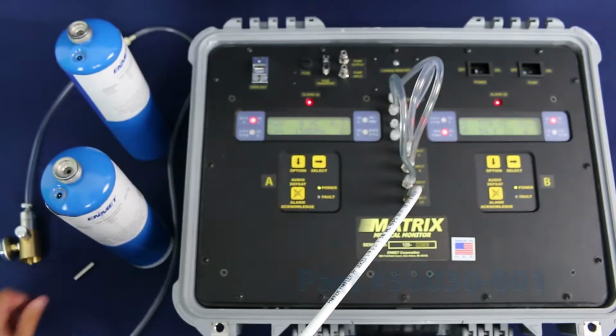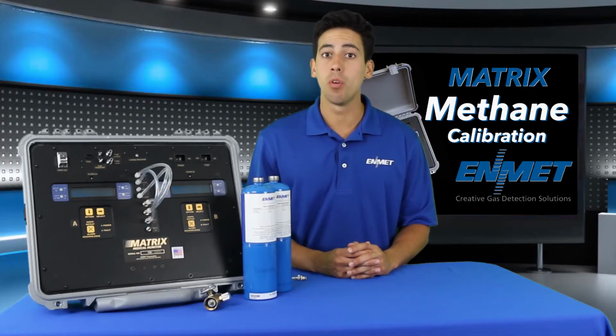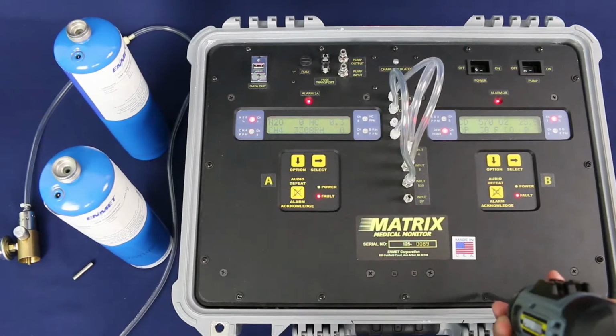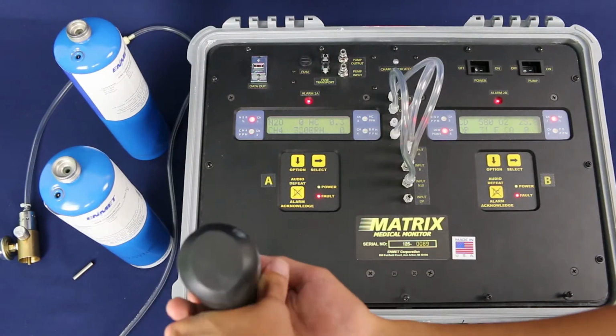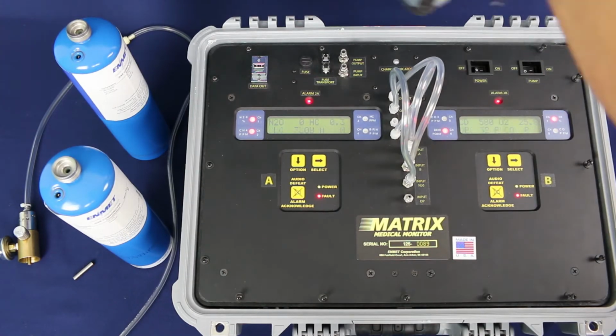The calibration of the methane channel must be performed via the internal sensor transmitter inside the matrix. In order to complete this calibration, the matrix main control panel must be open to access the methane sensor transmitter. To get to the transmitter, you must remove all the screws around the outside of the panel. There are 16 screws total that you should be removing.